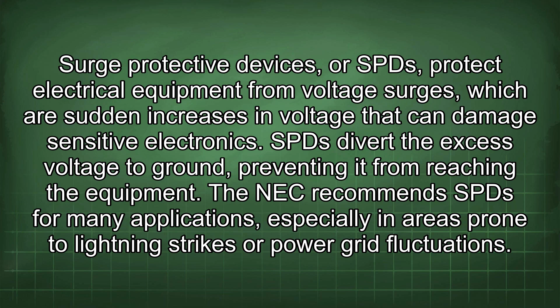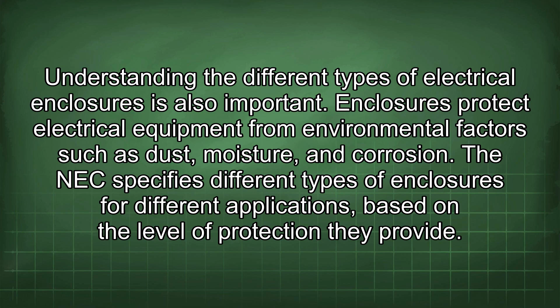Understanding the different types of electrical enclosures is also important. Enclosures protect electrical equipment from environmental factors such as dust, moisture, and corrosion. The NEC specifies different types of enclosures for different applications based on the level of protection they provide. For example, a NEMA 3R enclosure is suitable for outdoor use and protects against rain, while a NEMA 4X enclosure provides protection against corrosion and hose-directed water.